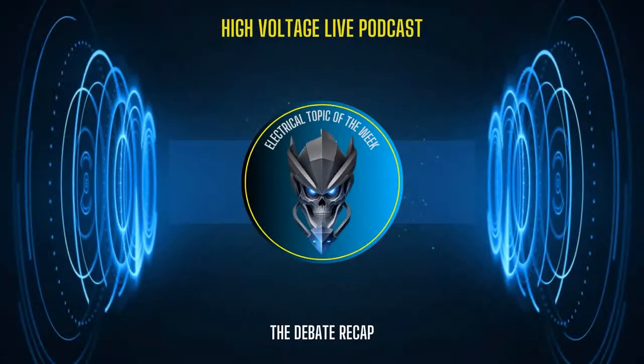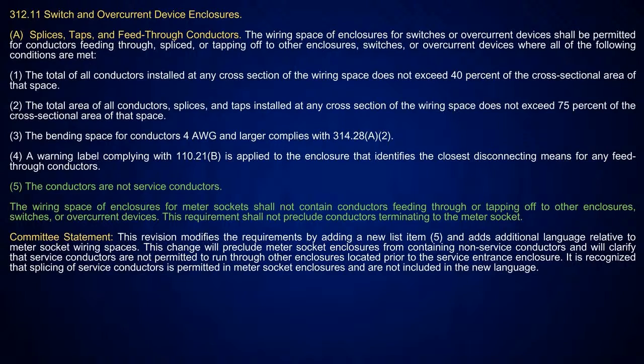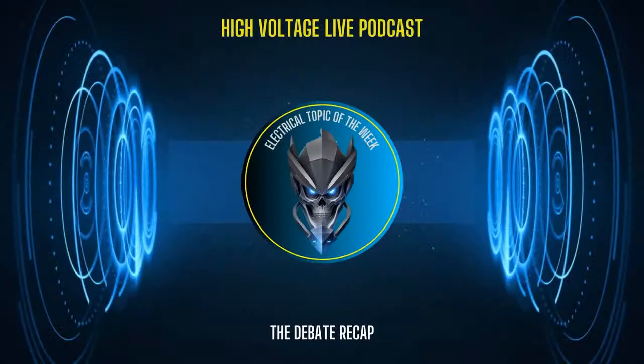Does that have anything to do with fused or unfused? Well, yeah, it would, because it's still a meter socket enclosure. Regardless, everything said here is about the wiring space of the enclosure for those meter sockets, and it's telling you what cannot be in those meter sockets. I think this helps clarify to make sure there are no other conductors in there. Because you could tap off the load side, and I guess it would be unfused. It's still part of the conductors that are permitted to be there. They're talking about other conductors, people running through there and using it as a junction box.